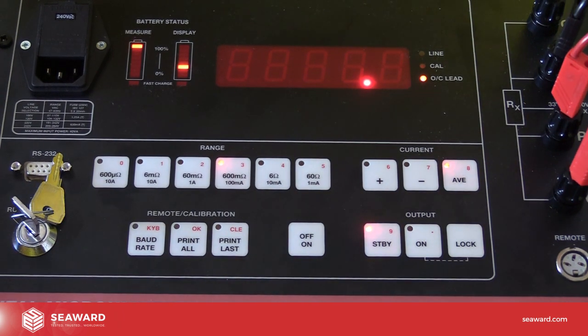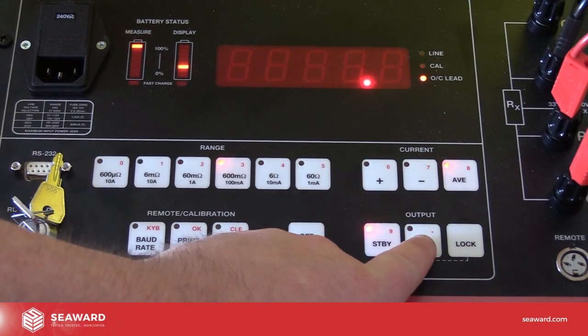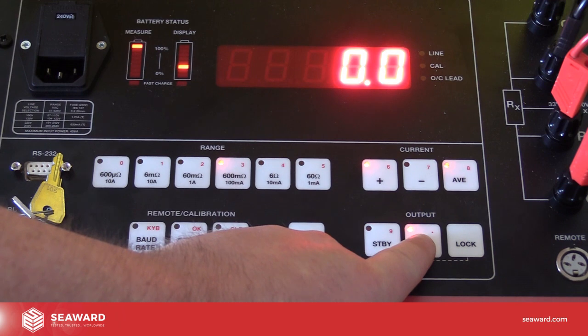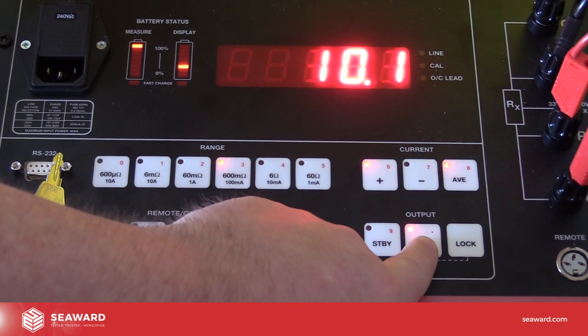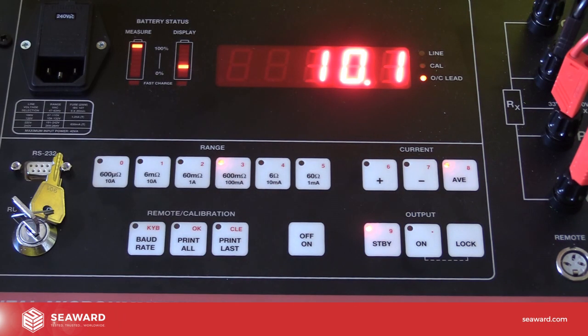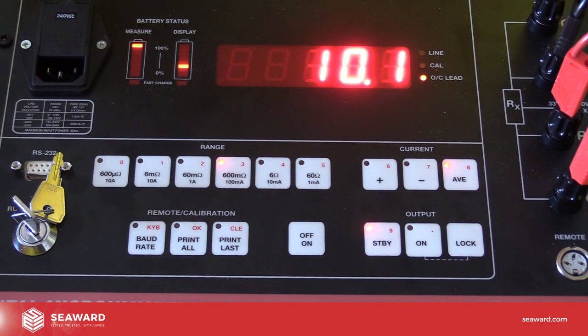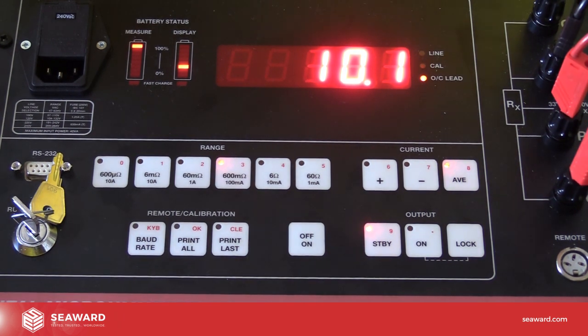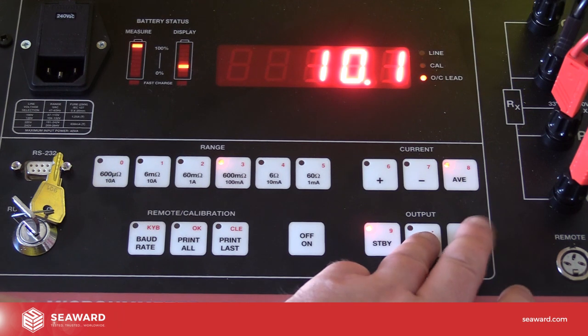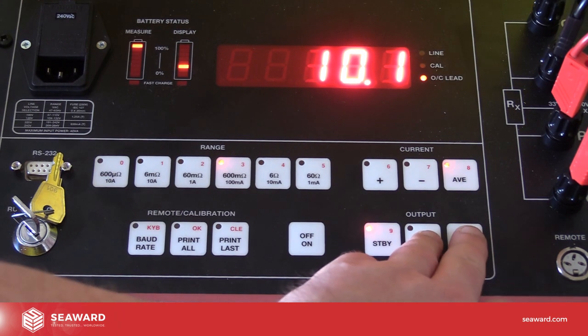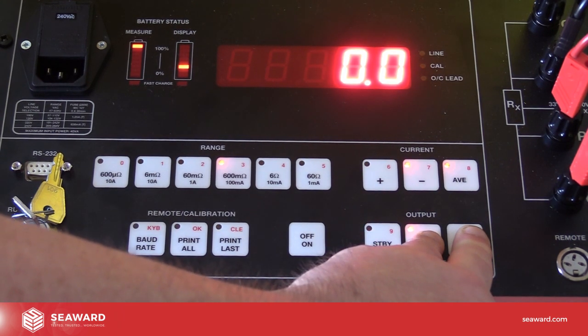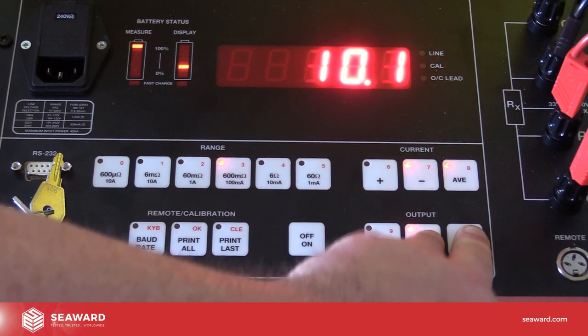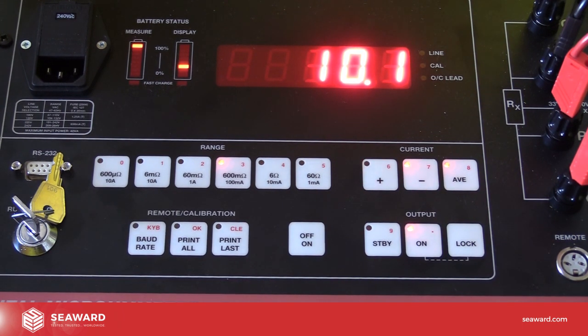So with everything now set up, I can simply take the measurement. In order to do that, I simply press and hold the on button. The current will go from positive to negative and then display me back the average reading. That reading will be held on screen for 30 seconds or until I press another button. However, should I wish to, I could also set that to a continuous measurement. In order to do that, I simply press and hold the on button with the lock button. And once the unit starts beeping, it's now constantly measuring.